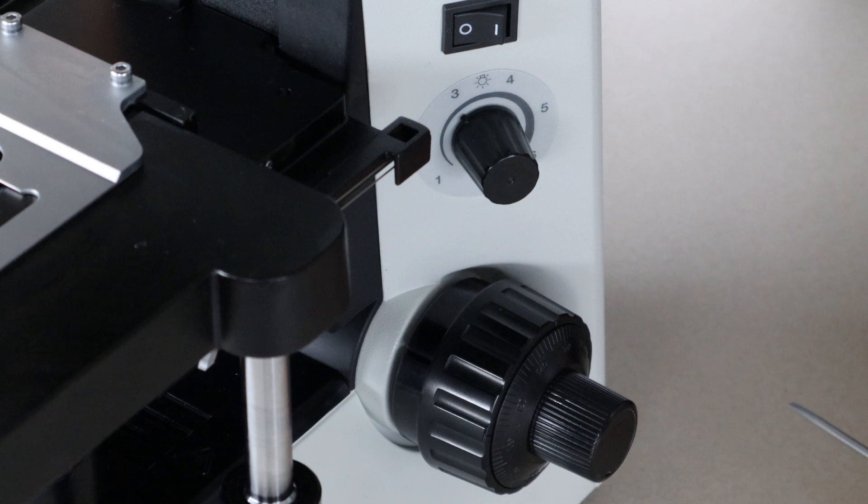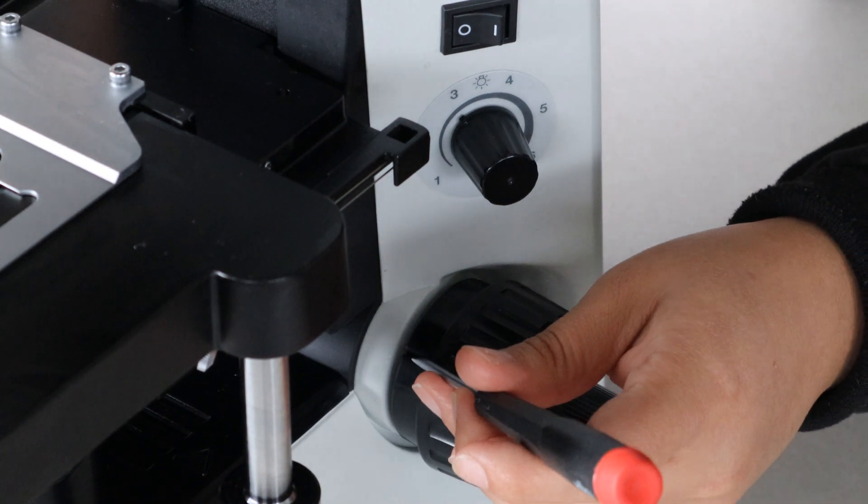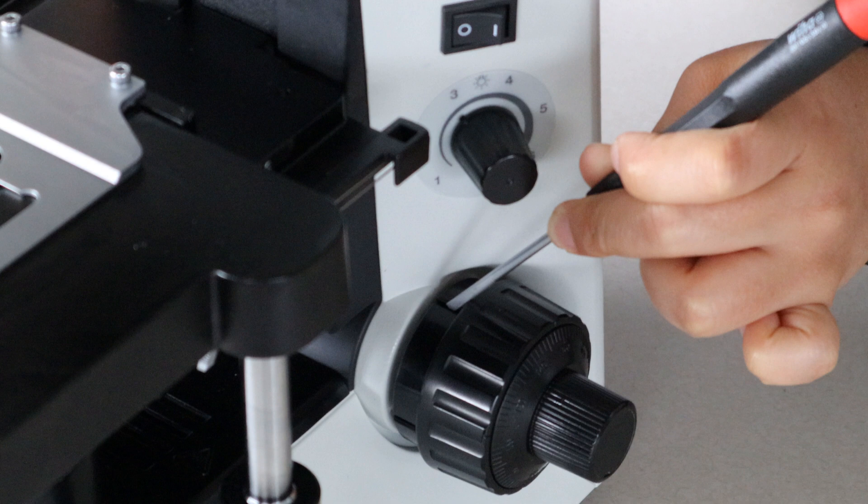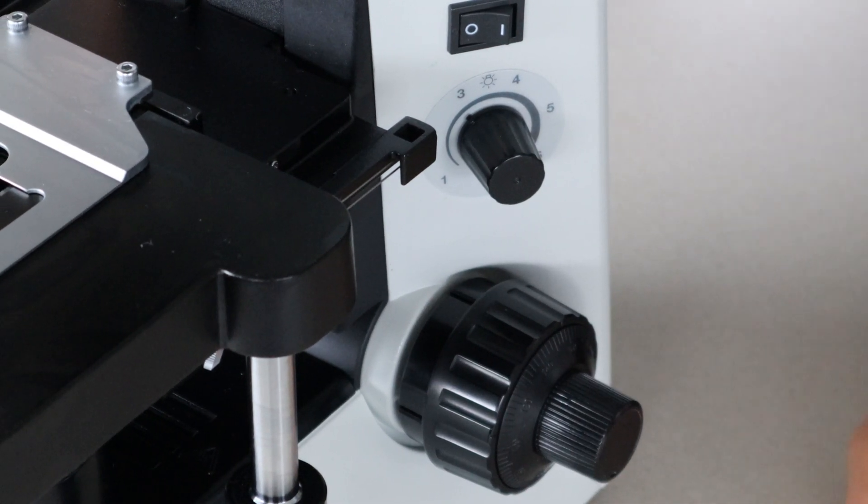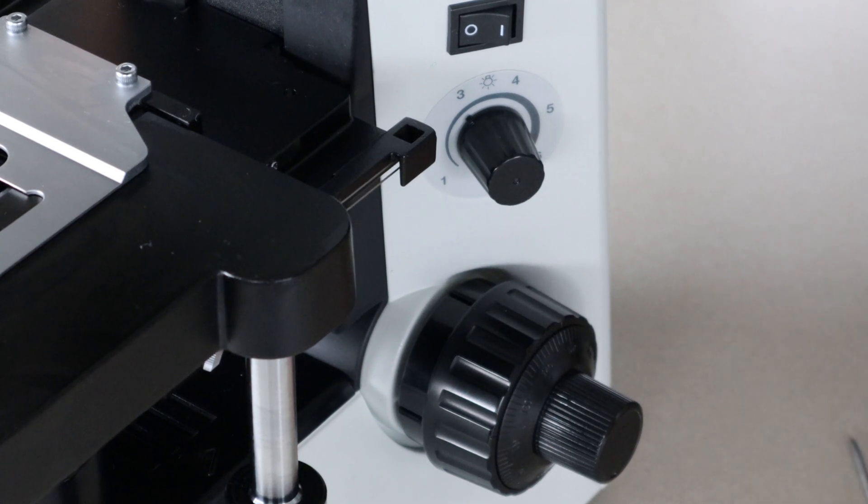And like we said, just an eighth to a quarter turn should be enough to get it to about where you want it. All right, and that was how you adjust the tension on your CX series microscope. If you have any questions, feel free to give us a shout. We're always happy to help. Thank you for watching.